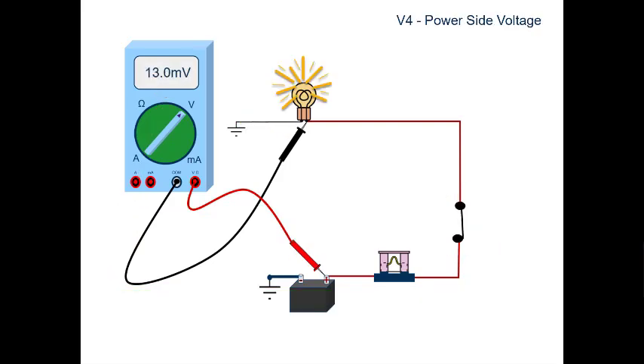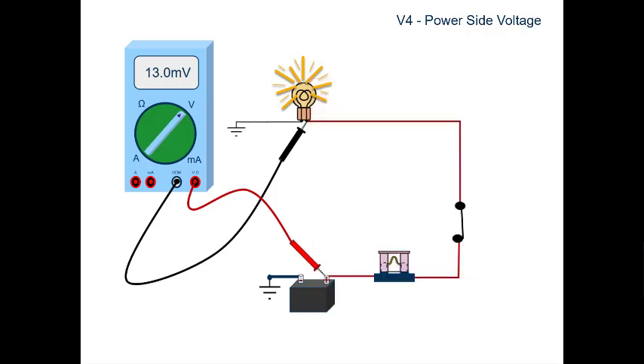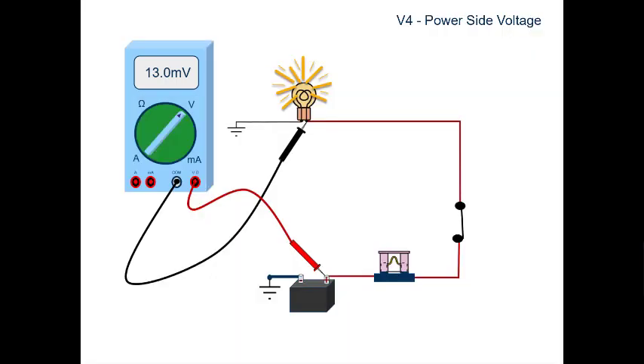This is the V4 portion of the V1 through V4 method. In this example, we are measuring the voltage on the power side. Just like in the V3 portion, in a working circuit with current flowing, we should see a very small amount of voltage on the meter. This tiny 13 millivolt amount represents the resistance in the wire. This is also called a voltage drop test.